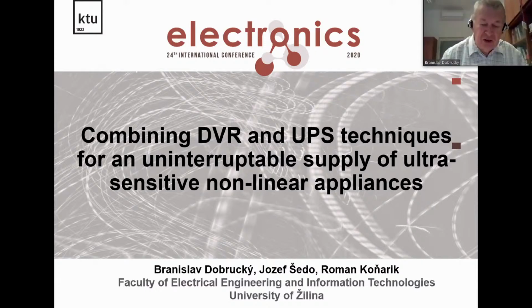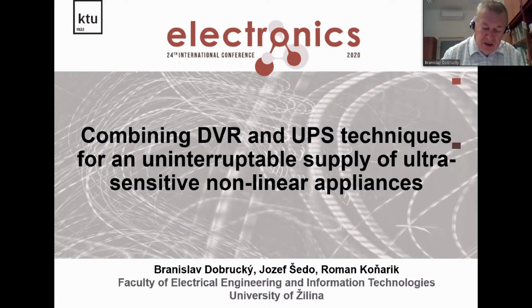My paper deals with an application of combined techniques of dynamic voltage restorer and uninterruptible power supply, which makes possible both short-time voltage sag compensation as well as longer power supply interruption under simultaneous operation of equipment and the network—that is, parallel operation. The combined technique is enabled mainly using instantaneous voltage detection and quick bidirectional power switches. It also needs a very fast control method which can provide voltage recovery for phase-sensitive loads within several calculation steps, so a deadbeat regulator is used. Such a system compensates even the influence of nonlinear loads on the power supply network.